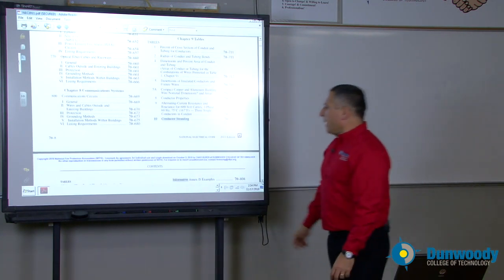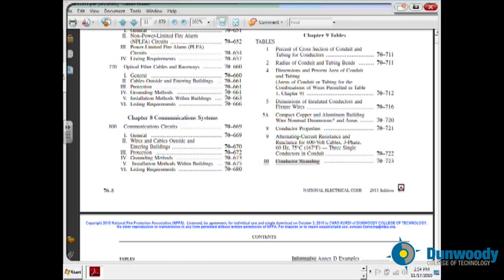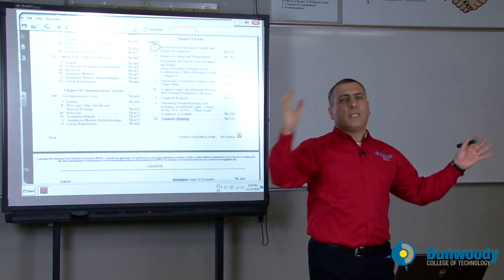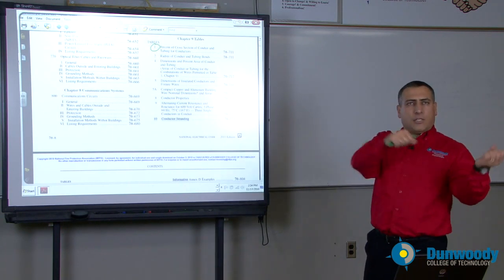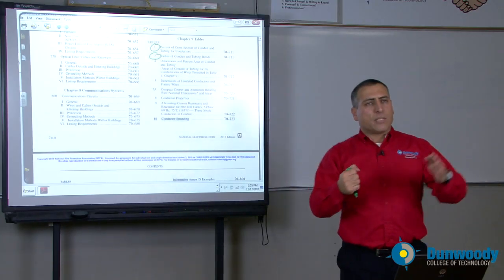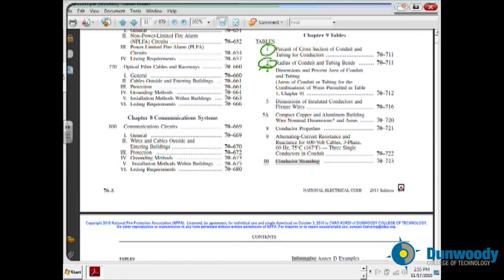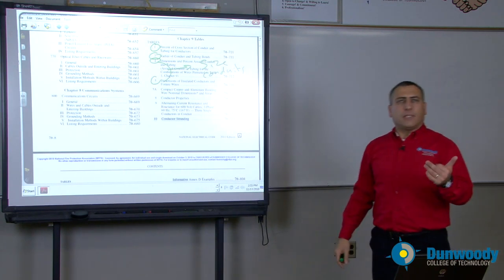Chapter 9 has tables that you need to be aware of. For example, how do you fill the percentage that you can fill of a conduit? A three-quarter inch conduit — you can only fill 40% of it. The 60% is sitting there empty because of heat dissipation and ease of installation. Bending radius: if you have a 6-inch rigid metal conduit steel, what's the smallest radius that you can bend? You'll find it right in here. Table 4 and 5 are very important and will help us size conduits based on branch circuits, feeders, and service entrance conductors, with different insulation and different sizes.